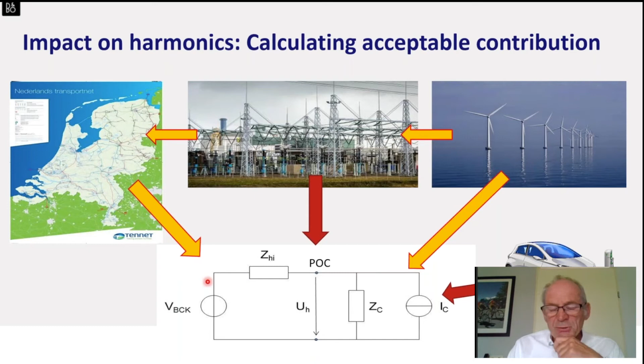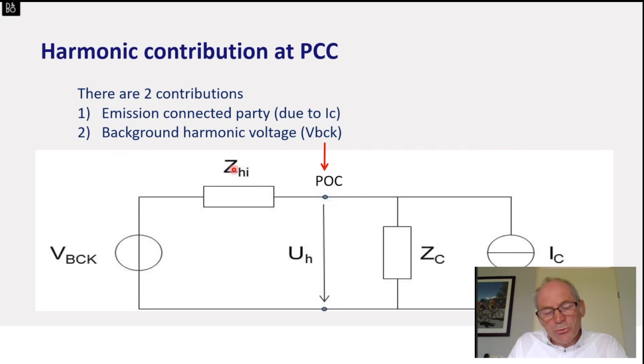So it's not only the harmonic current from the load side or from the solar systems or whatever, it is also the harmonic background that was already existing from all the other customers connected to the network. And the impedance of the network itself is also not a constant value, because the net configuration could change, but also all the load that is connected to the network is somewhere in this impedance. So what is normally done by the TSO is that they give a whole envelope of possible impedances in the network, depending on the state of the network, for all frequencies. So for the first to the fifth harmonic, the fifth to the 10th harmonic, and so on. And then the customer has to calculate, with the harmonic current that he is injecting into the network, if he is still complying with the harmonic voltages that may occur at the point of connection.